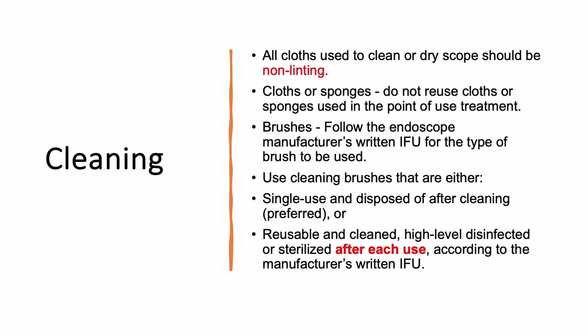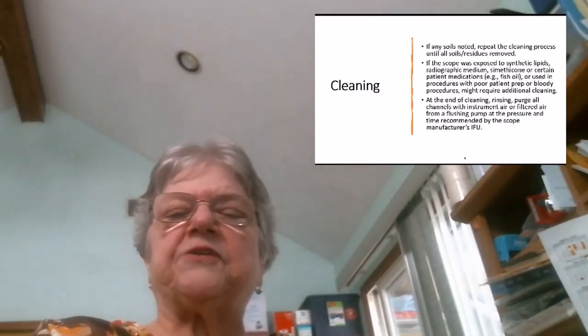Any quality assurance testing that's recommended by the manufacturer, like the daily volume verification, should be performed and documented. After cleaning and rinsing, inspect the scope, and if using disposable tubing on your unit, change it as recommended. If any soils are noted, repeat the cleaning process until oils, soils, and residue are removed. If the scope is exposed to any synthetic lipids, radiographic medium, simethicone, or certain patient medications such as fish oil, or used in procedures where the patient had a poor prep or bloody procedures, these scopes will probably or might require additional cleaning. At the end of cleaning and rinsing, purge all channels with instrument air or filtered air from a flushing pump at the pressure and time recommended by the scope manufacturer's instructions.